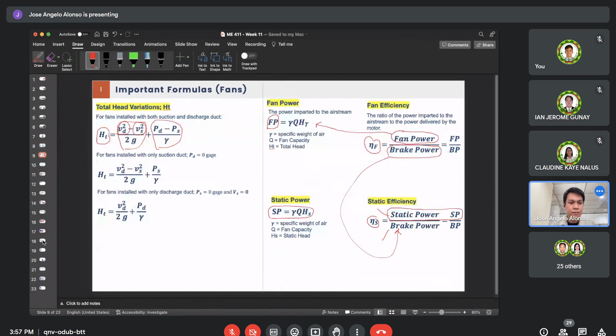For example 3.0: a small blower handles 44 cubic meters per minute of air. The problem gave us the volume flow rate of 44 cubic meters per minute, whose density is 1.169 kilogram per cubic meter — so the problem also gave us the density. The static and velocity heads given are 1,605 Pascal and 120 Pascal, with water as the gauge fluid. However, since the given pressure's reference is water gauge, we need to convert that into pressure of air or head of air. The temperature is 15.56 degrees Celsius.